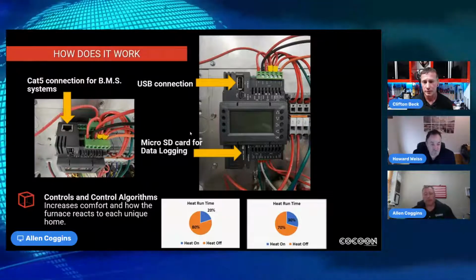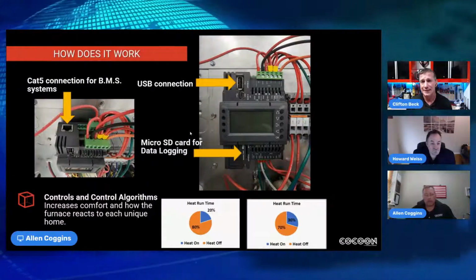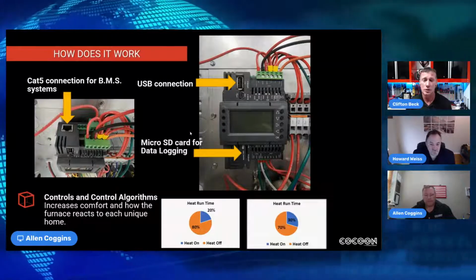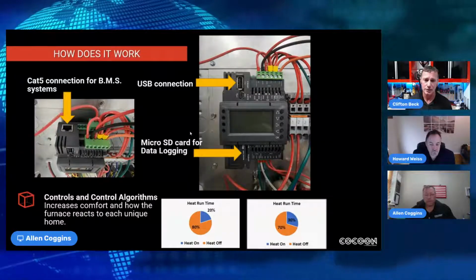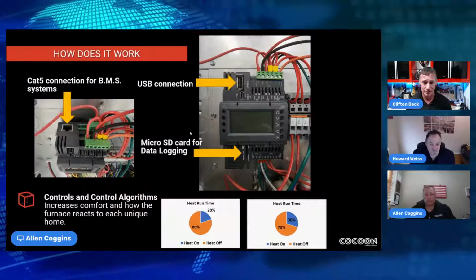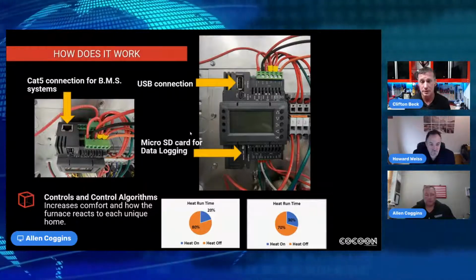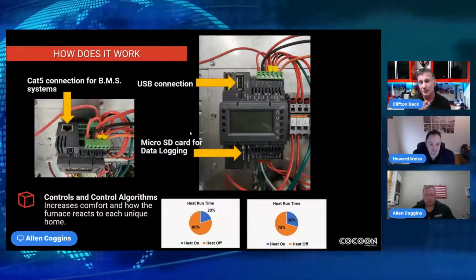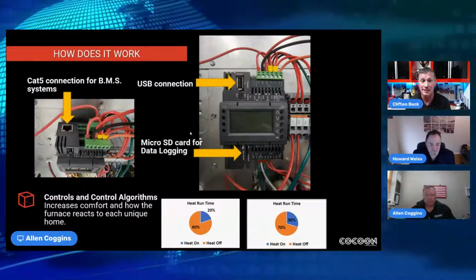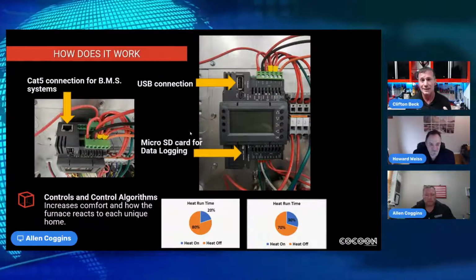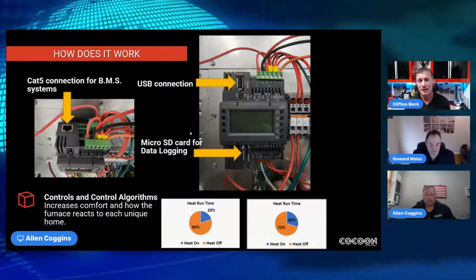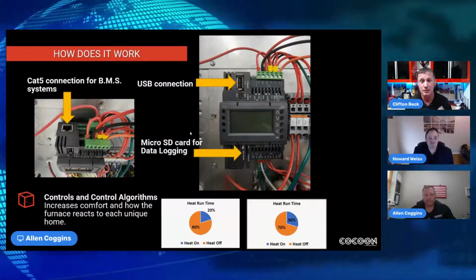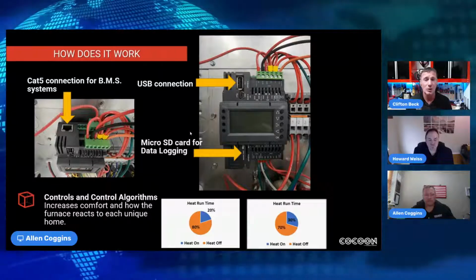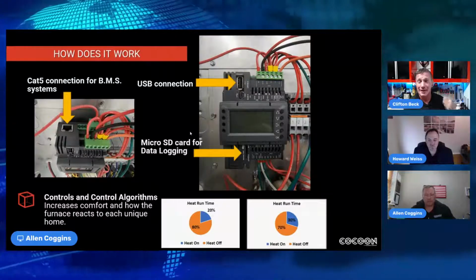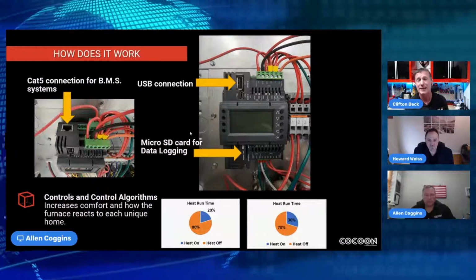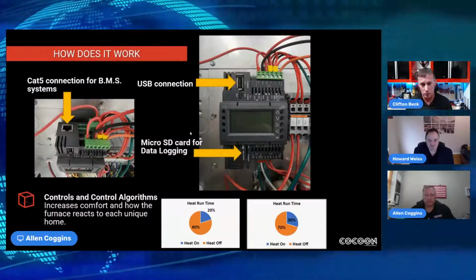One trend in the industry I really struggle with is electric furnace manufacturers bringing on all banks of electric resistive heating when it calls for auxiliary heat. There was a time, a couple decades ago, where the HVAC technician would design how to stage in the electric heat and determine how much was needed for defrost cycles. That's gone away, so a lot of our electric furnaces just slam on 100% of the electric heat instead of doing controlled staging.